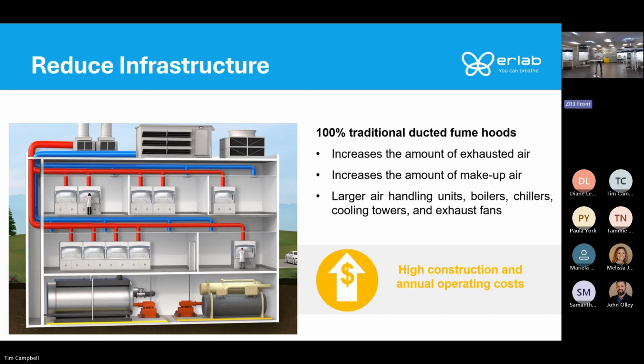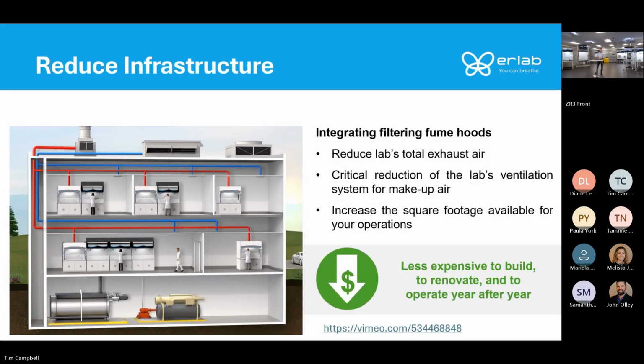Now, instead of designing with 100% ducted fume hoods, let's go 50-50. Do 50% ducted fume hoods, 50% ductless fume hoods. You're going to see a significant reduction in the total exhaust air that's needed. That's also going to allow you to reduce your air handling unit, your exhaust fans, your cooling tower, the size of your chiller and your boiler. It's going to significantly reduce the upfront cost because all that mechanical equipment is going to be reduced. But then moving forward, it's going to reduce your maintenance because you're going to be maintaining smaller equipment.